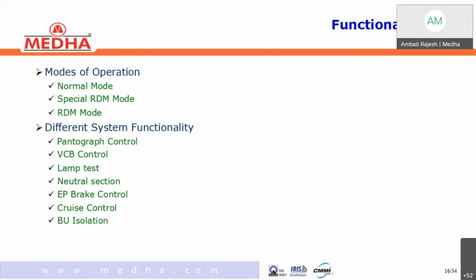That is one case. Another case is where the neutral section is not available, but the operator accidentally or unknowingly presses the ENS switch. After 250 meters, the system opens the VCB, but it monitors the OHE voltage continuously. If the OHE voltage is available continuously, then after 500 meters it will exit the neutral section logic, as it is a wrong operation, a wrong command.